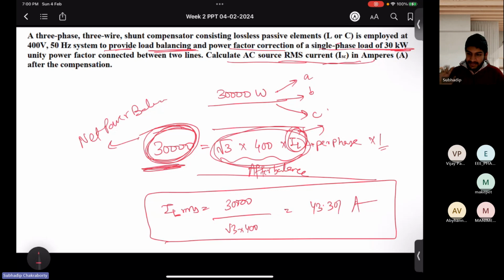What I am telling is, a single phase load is there, but this single phase loading on 2 lines has to be made in such a way by compensation that it comes on 3 lines. This is the meaning of load balancing. Even if only a single phase load is there between 2 lines, for example A and B, you have to provide compensation and do load balancing, such that loading is borne by 3 lines equally. Single phase load, agreed, but the total loading of 30 kilowatt needs to be split among 3 lines. So assuming that you have already designed compensators to balance the 30 kilowatt load on the 3 lines, your 3-phase power still remains 30 kilowatts on the 3 lines, even if it is a single phase load. The best technique to use here is the power balance.